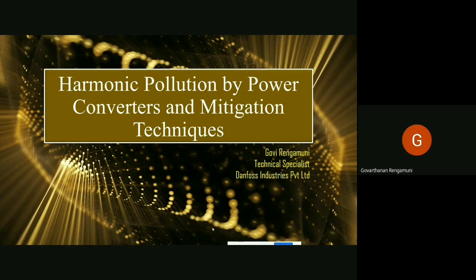Here, what is power quality? Power quality is a concern on maintaining an undistorted voltage at the grid level. The undistorted voltage depends on many factors. The factors are the type of loads connected in the grid, the importance of the grid, the turn on and turn off sequence of the load, and the injected current distortion. The injected current distortion is due to the harmonics injected from various types of loads, mainly the power converters. Today, this topic will be towards that one only. That means we are going to discuss all about the harmonic emissions from the power converters.